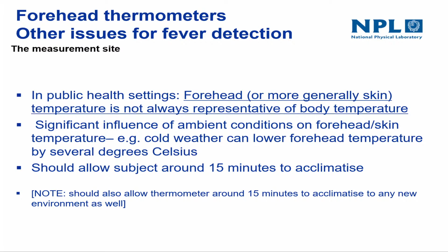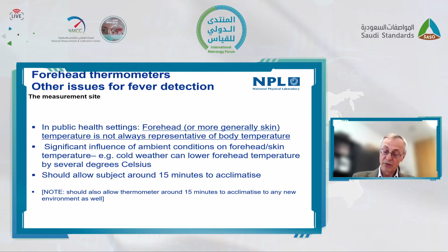That's because they'd been outside in the cold weather in the UK. So you really need to let someone acclimatise for at least 15 minutes in a sensible ambient environment before you use a forehead thermometer. But even if you do that, it's important to keep in mind that the forehead is not always representative of body temperature.